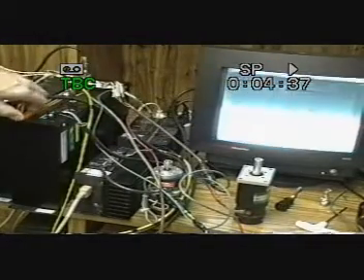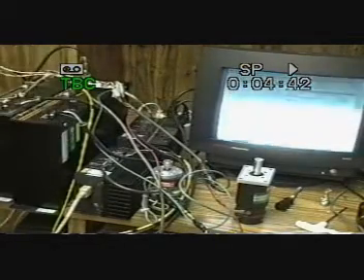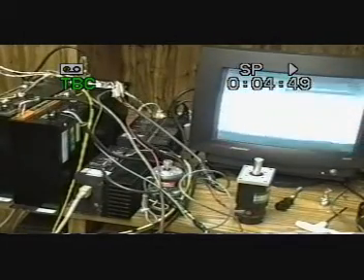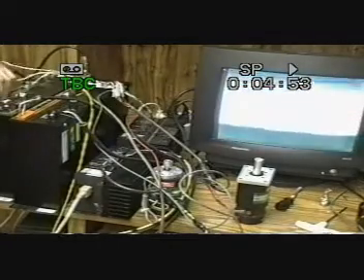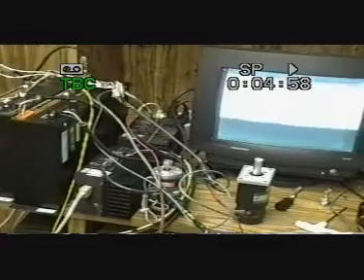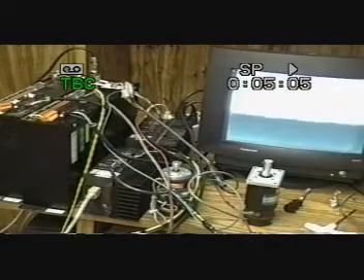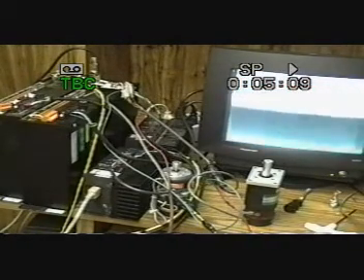I can enable and disable like your gripper does, and we can turn your gripper motor on and off, and you'll see that that follows it. I can turn the master press on and off, and you can see that that follows it also. All that would lead me to the conclusion that your controller is okay, your gripper motor is okay, and the program within it is not.